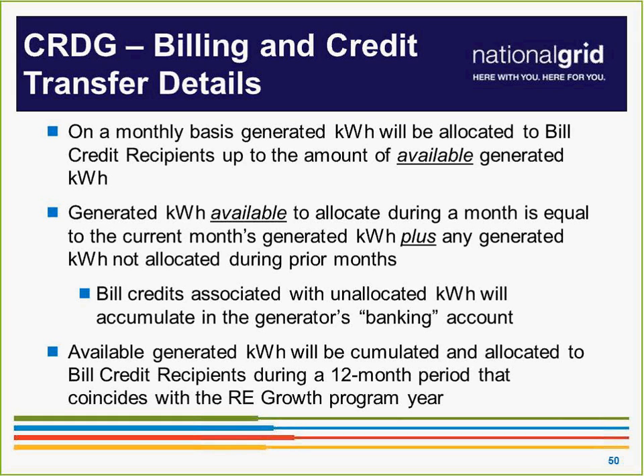It's calculated on a monthly basis. So during a month, it is equal to the current month's generation plus any generated kilowatt hours not allocated, calculated and allocated to the recipient during a 12-month period that coincides with the program.